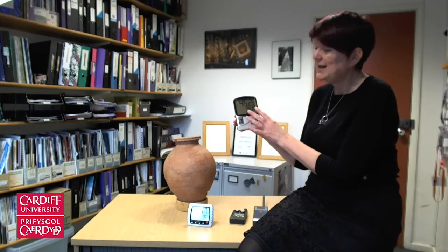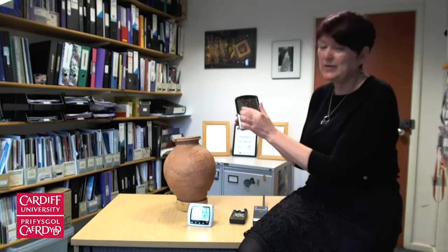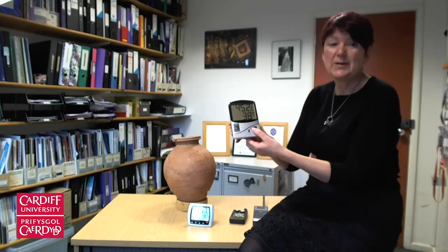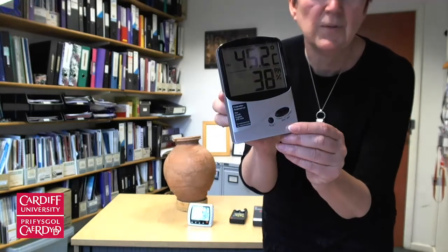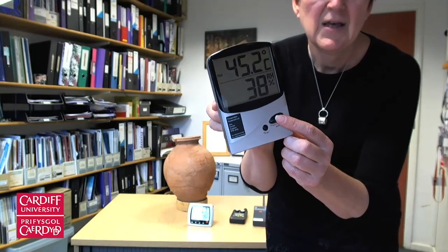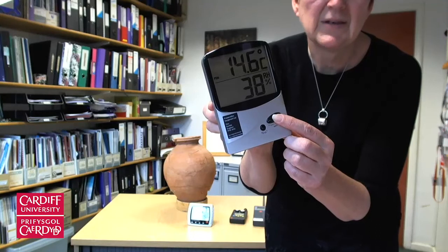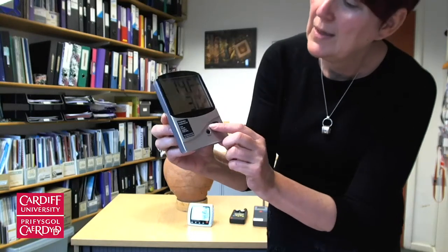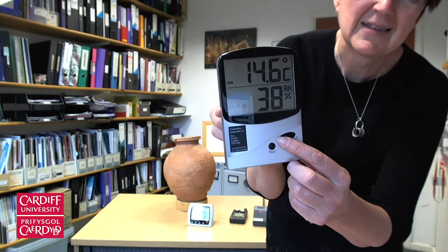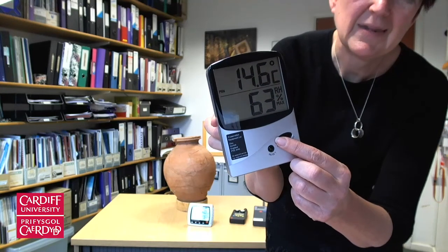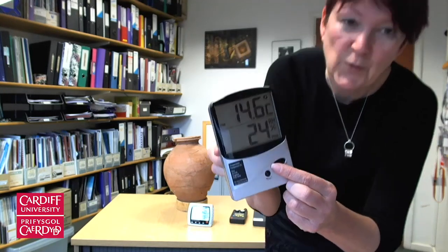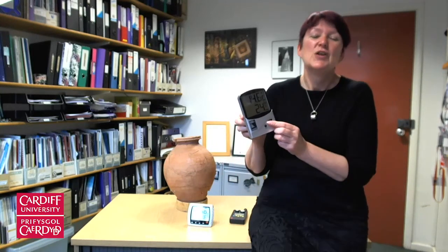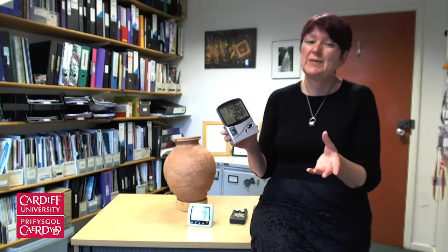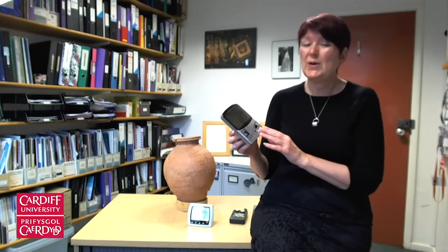But they also tell you a little bit more information. They tell you what the humidity is currently. They also have a button on them. This one I think I can show you. A maximum and minimum button that you can find out what the maximum conditions were since you were last there. So since I last reset this, it's currently 38%. It's been 63% and it's been 24%. Sorry, I jumped out of screen. So that means that since I last reset this, the space has fluctuated between 24% relative humidity and 63%, which is quite a big fluctuation and something you need to know about.